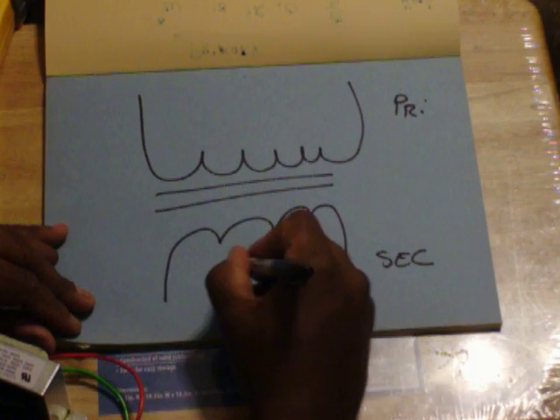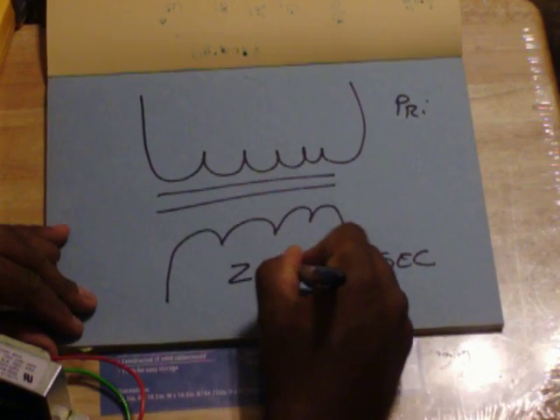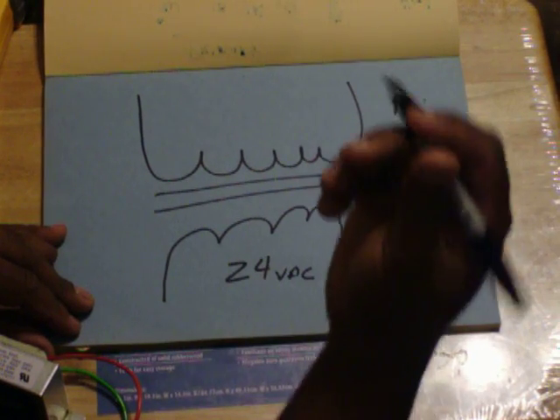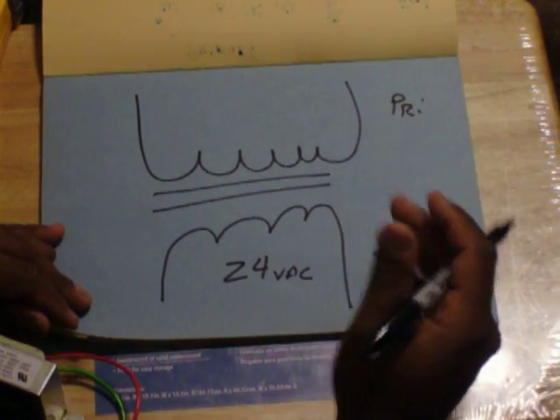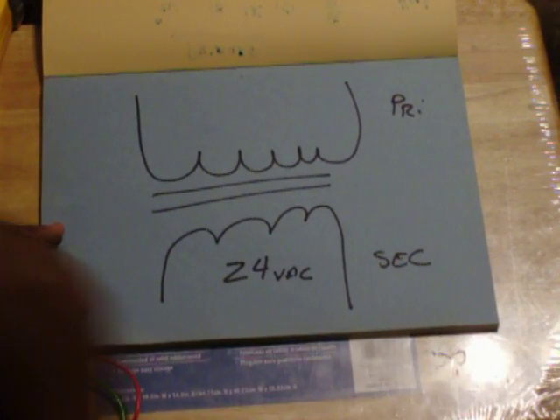For air conditioning, your secondary voltage is 24 volts AC. Now, in your primary, you could apply 110 volts, 208, 230 volts, but make sure you have the right transformer.